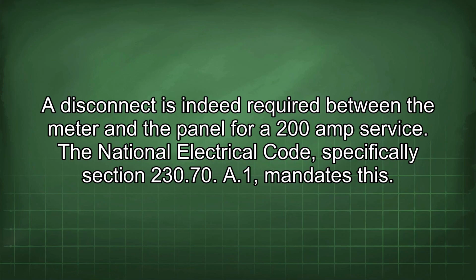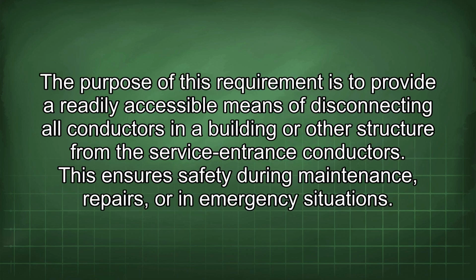A disconnect is indeed required between the meter and the panel for a 200 amp service. The National Electrical Code, specifically Section 230.70(A)(1), mandates this. The purpose of this requirement is to provide a readily accessible means of disconnecting all conductors in a building or other structure from the service entrance conductors. This ensures safety during maintenance, repairs, or in emergency situations.